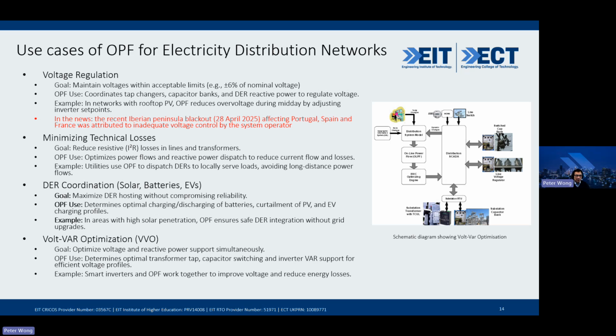Examples of OPF use cases could be networks with rooftop solar PV systems. OPF will reduce the overvoltage during midday by adjusting inverter set points. So when you have a voltage rise from a lot of generation on the distribution network, not much load, you can use OPF to determine the appropriate settings for whatever equipment can provide reactive support.